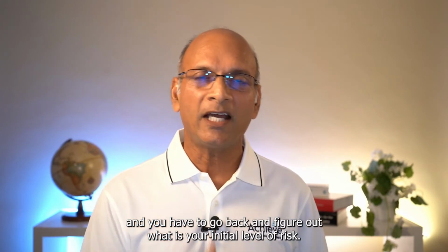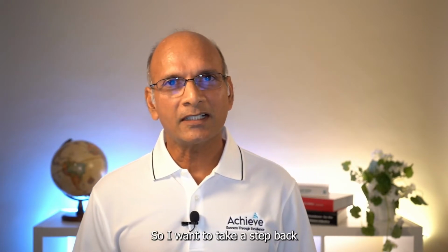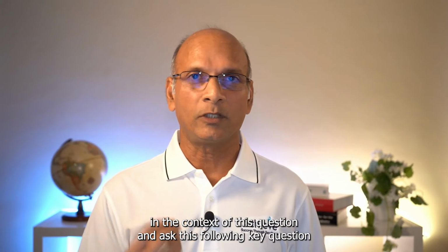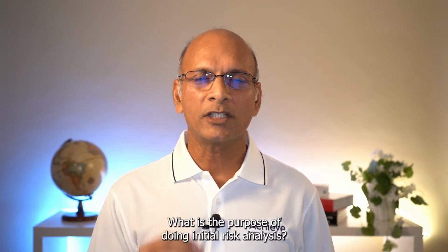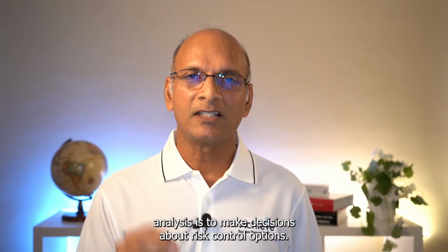And you have to go back and figure out what is your initial level of risk. So I want to take a step back in the context of this question and ask this following key question. Why are we required to do initial risk analysis in ISO 14971? What is the main reason? What is the purpose of doing initial risk analysis? The purpose of initial risk analysis is to make decisions about risk control options.